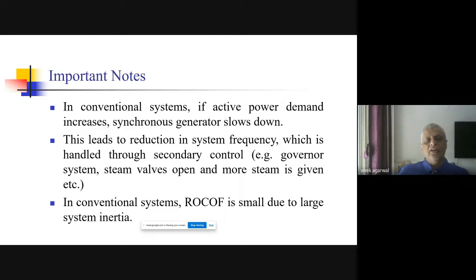So this leads to a reduction in the system frequency, which is handled through some secondary control, like the governor system of the synchronous generators. They will open up the steam valve, inject more steam, and restore the power. So they will start generating the active power demand that is there on the grid, and the synchronous generator will come back to its original speed. This is how it will work.